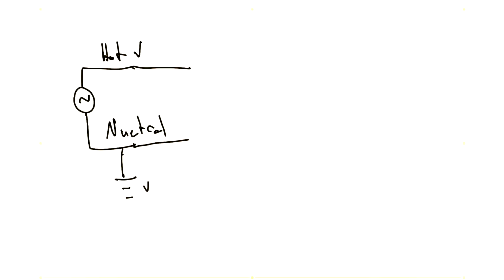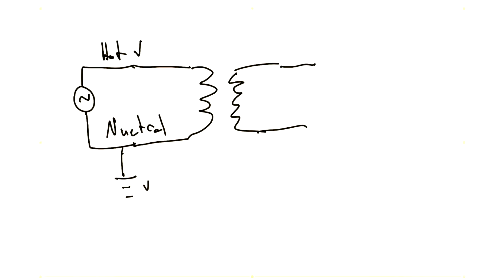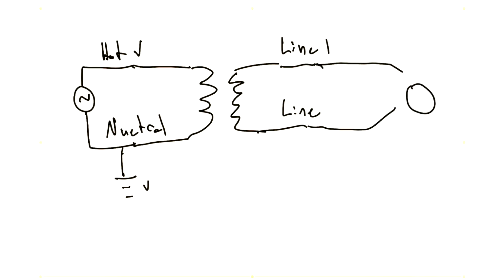Now let's take a look at our isolated system. We get an isolated system by using something called a transformer. I'm not going to go into how these transformers are designed because they can be designed differently, and each company has its own nuances to transformer design for isolated systems. But they're all physically separated from line voltage. That's what the transformer allows us to do. So in an isolated system, there's a physical separation between line voltage and our isolated system. And we'll usually label line one and line two of our new circuit, and those are connected to our breakers and to our outlets.